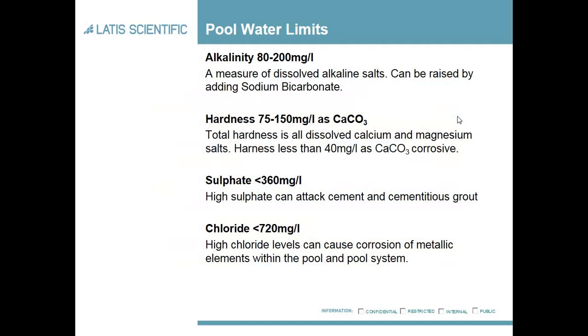So the chemistry of the pool — there are some main constituents that we look for. The first one is alkalinity. Alkalinity is a measure of the bicarbonate and carbonate hydroxide content. The higher the alkalinity, the more resistant the pH change will be. The range we look for is between 80 to 200 milligrams per litre. If it's below 80 you will often find you get pH bounce or rapid changes in pH.